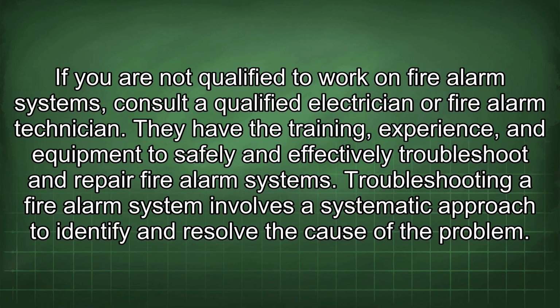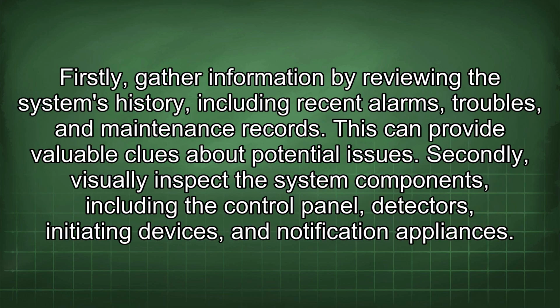Troubleshooting a fire alarm system involves a systematic approach to identify and resolve the cause of the problem. Firstly, gather information by reviewing the system's history, including recent alarms, troubles, and maintenance records. This can provide valuable clues about potential issues.